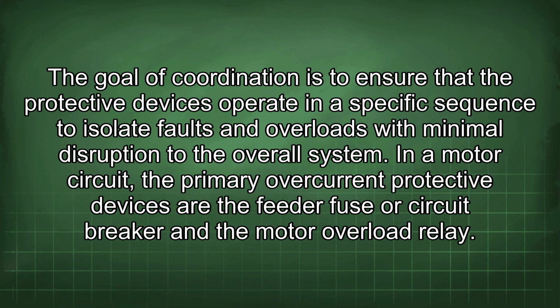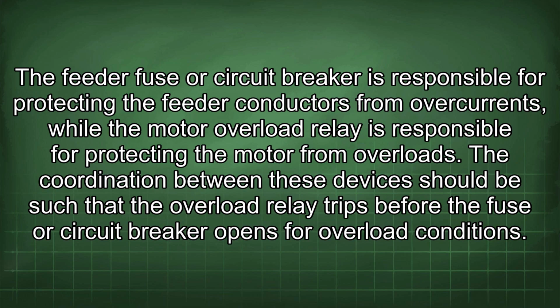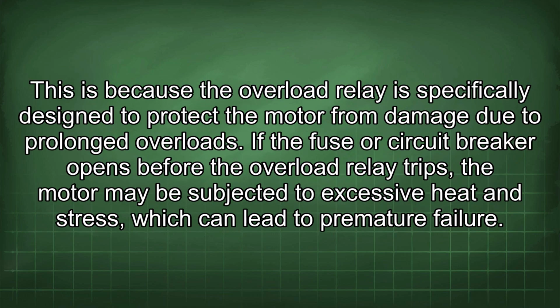In a motor circuit, the primary overcurrent protective devices are the feeder fuse or circuit breaker and the motor overload relay. The feeder fuse or circuit breaker is responsible for protecting the feeder conductors from overcurrents, while the motor overload relay is responsible for protecting the motor from overloads. The coordination between these devices should be such that the overload relay trips before the fuse or circuit breaker opens for overload conditions. This is because the overload relay is specifically designed to protect the motor from damage due to prolonged overloads. If the fuse or circuit breaker opens before the overload relay trips, the motor may be subjected to excessive heat and stress, which can lead to premature failure.